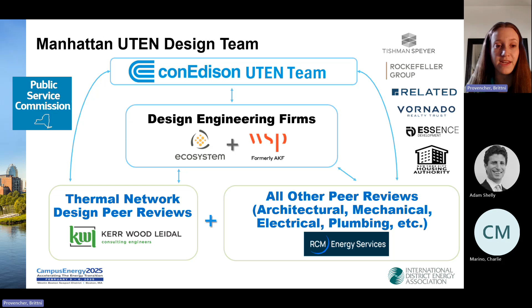The first of our 2 Manhattan pilot projects is in Chelsea. Our Chelsea project captures waste heat from a commercial office building with a data center in it, located at 85 10th Avenue. We tap into the condenser water return in the building's chilled water plant to provide heat to the UTEN, and we'd use the building's cooling towers if we need to reject any heat from the system.